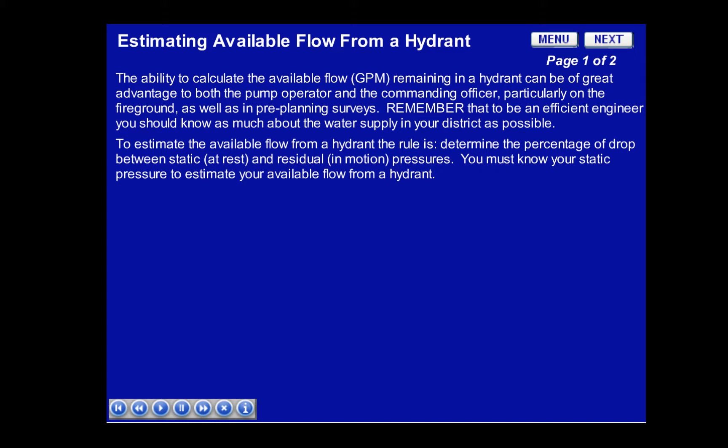To estimate the available flow from a hydrant, the rule is to determine the percentage of drop between static — at rest — and residual in motion pressures. You must know your static pressure to estimate your available flow from a hydrant.